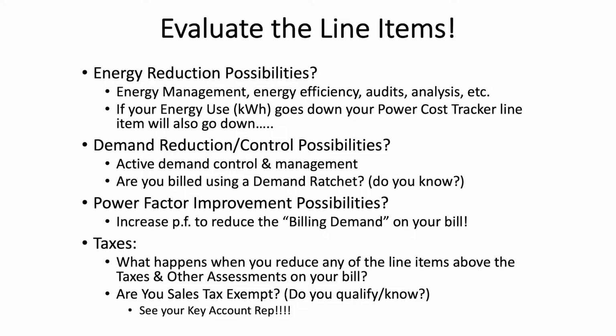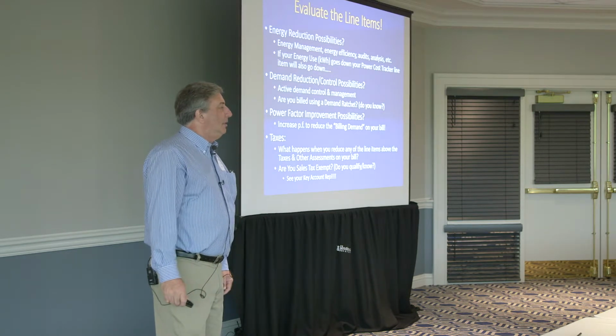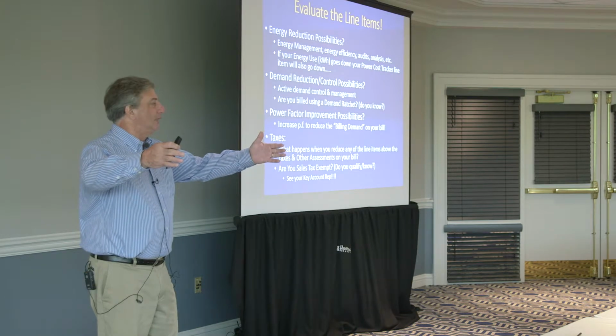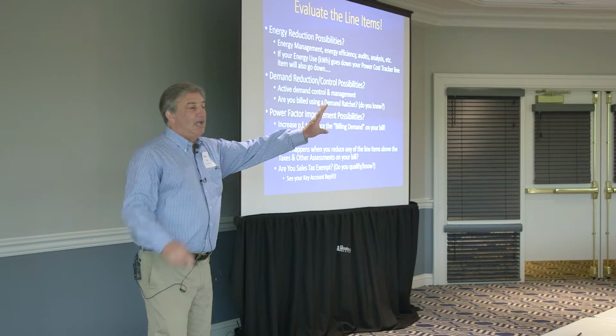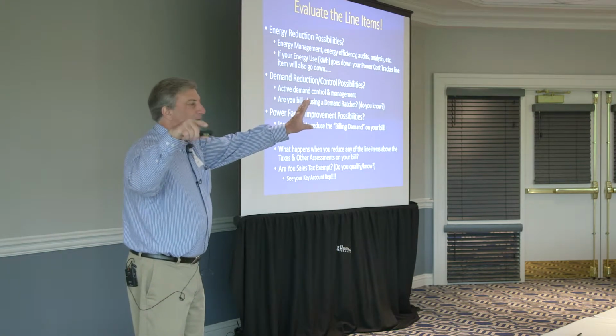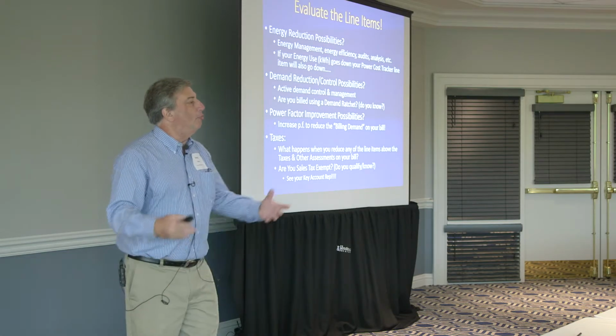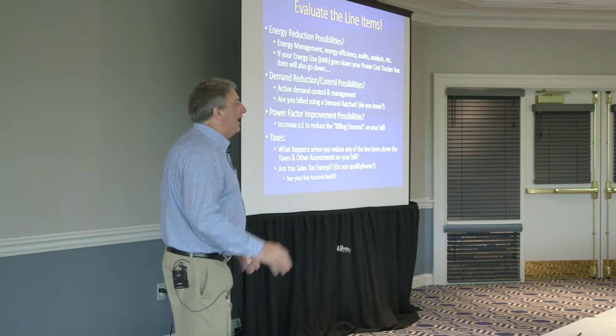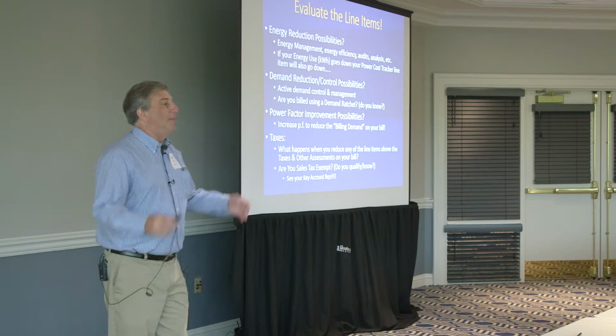Demand reduction and control possibilities: there are all kinds of active demand management strategies used today. Some are as simple as training employees—if this piece of equipment is running, never turn this other one on at the same time, because it'll set a big peak demand we don't want to pay for. But even with a written standard operating procedure, can people still screw up? Potentially. So some companies use demand lockouts—mechanical or electronic devices that prevent one piece of equipment from starting if another is already on, taking the chance of human error out of the employee's hands unless they bypass the device.